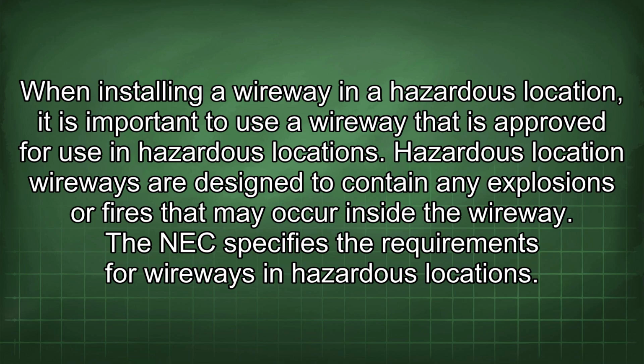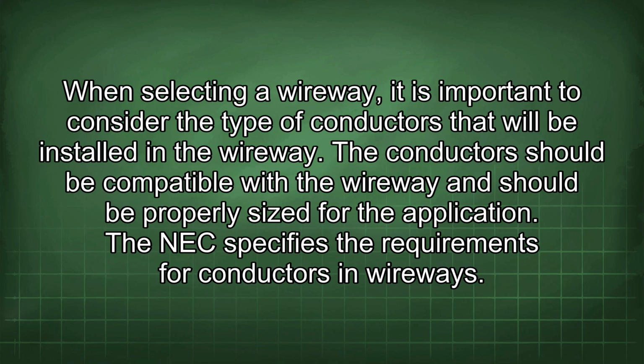When installing a wireway in a hazardous location, it is important to use a wireway that is approved for use in hazardous locations. Hazardous location wireways are designed to contain any explosions or fires that may occur inside the wireway. The NEC specifies the requirements for wireways in hazardous locations. When selecting a wireway, it is important to consider the type of conductors that will be installed in the wireway. The conductors should be compatible with the wireway and should be properly sized for the application. The NEC specifies the requirements for conductors in wireways.